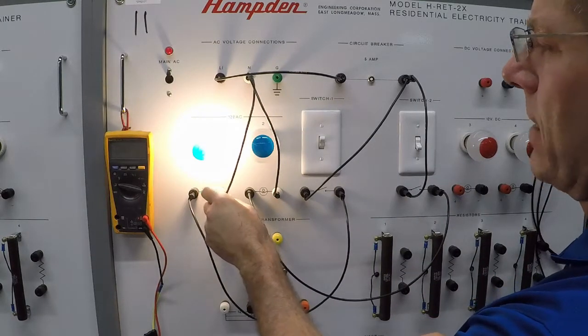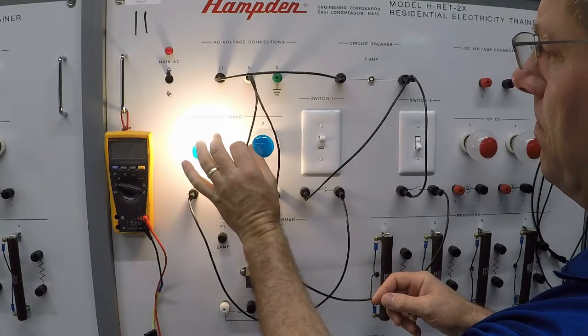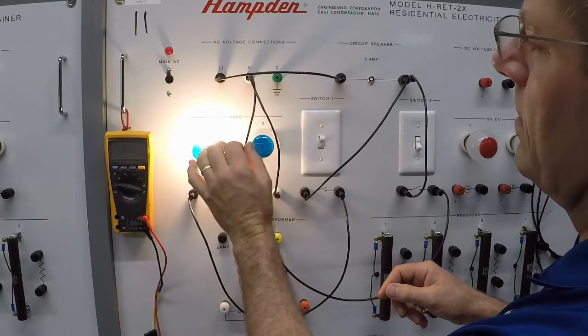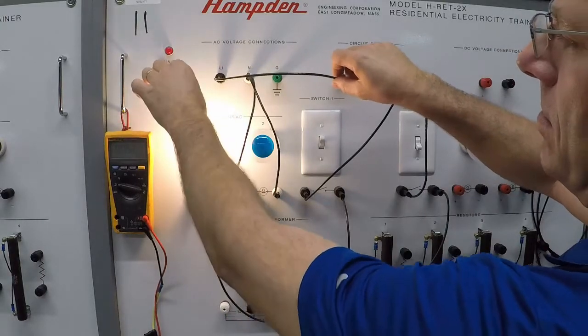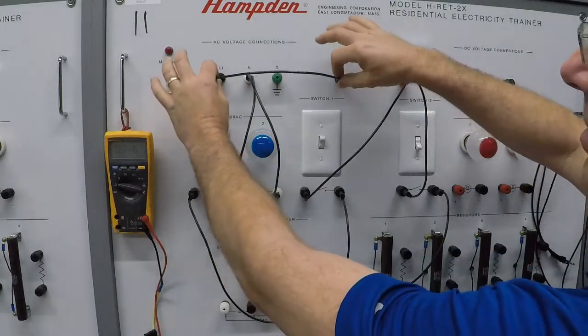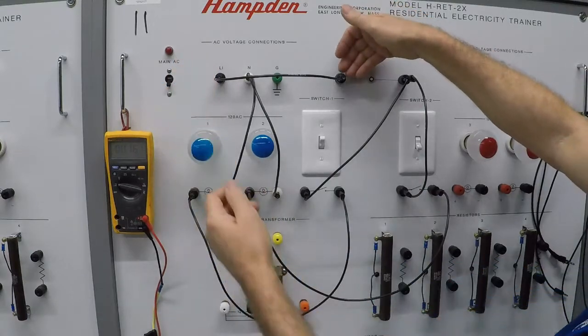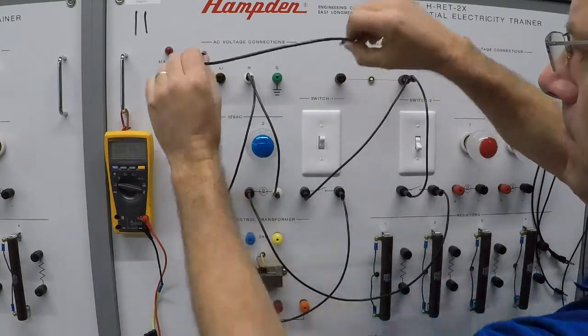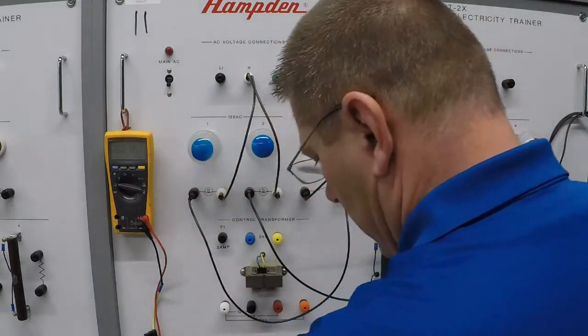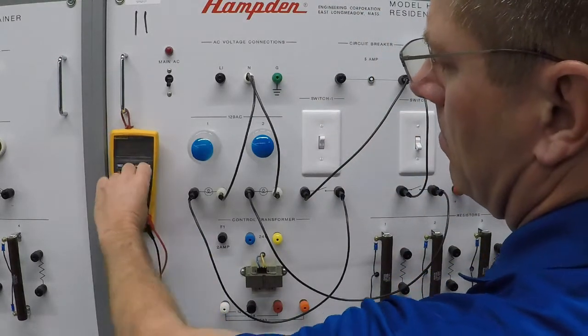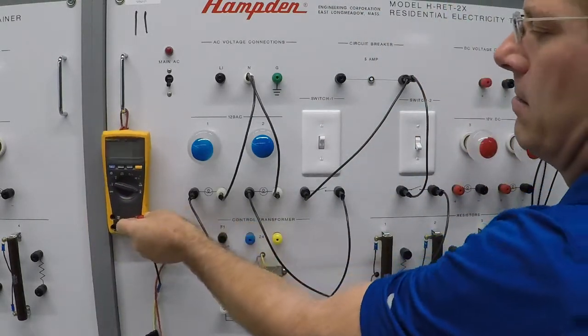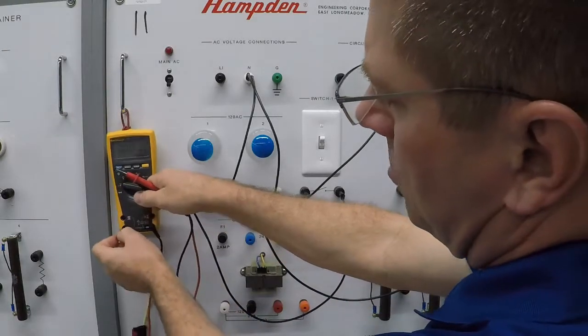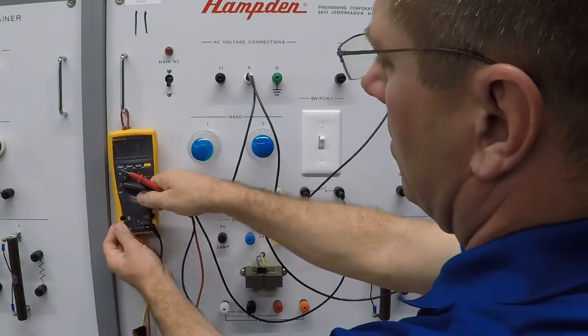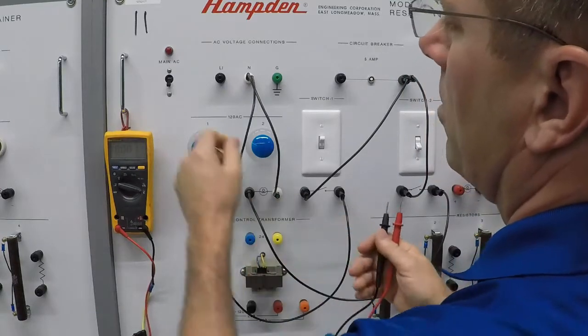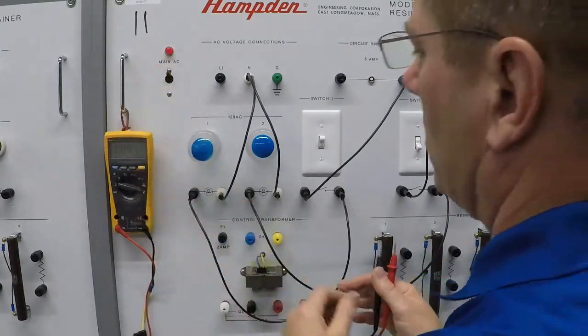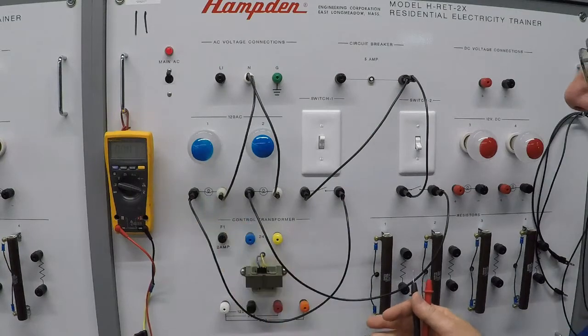So let's go back, leaving this connected. We're going to disconnect, turn off our power. We're going to disconnect L1 to our circuit breaker. We will place the meter back in the current measurement mode. Turn our main power switch back on. You notice that the light bulb did not illuminate.